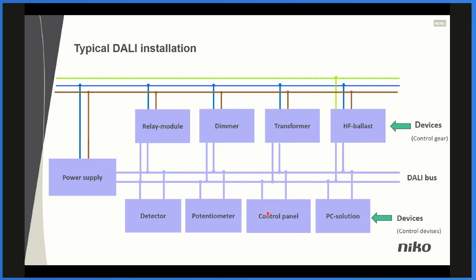The devices that we have, we divide them into 2 different types. We have all the devices that are connected to the mains. That means the 230 volt. And this is all we have here. It could be a relay, it could be a dimmer, a transformer, it could be a ballast, whatever. This we call the control gear. In order to control these devices, we have what are called control devices here. And this could be a detector, potentiometer, or whatever. This was what we call the original basis for DALI.